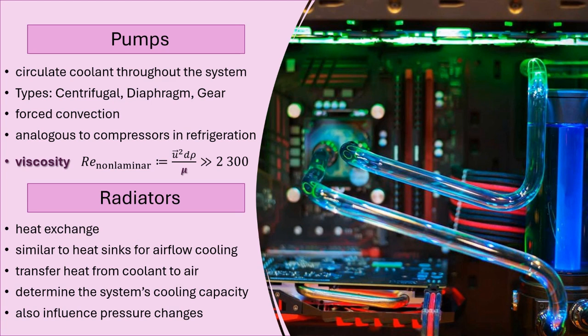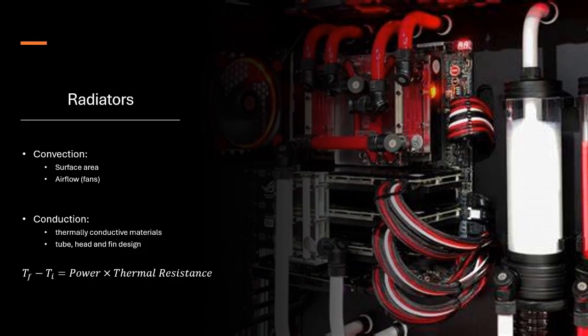The viscosity of coolants in these coolant-based temperature-controlled systems is relatively low, especially when compared to coolants in refrigerators, for example. The reason for this is both practical and economic. Some reasons are temperature and flow-related aspects. Coolants here operate within a narrow temperature range and, of course, need to be optimized for turbulent flow. Now, the benefits of having more turbulent flow present include enhanced heat transfer and increased convection. Low viscosity coolants assist in the creation of these circumstances by decreasing the denominator in the Reynolds number definition. And of course, less viscous coolants require less energy to initiate movement.